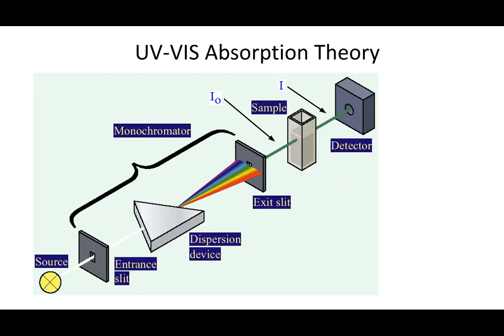The way UV-visible absorption spectroscopy works is you have a light source. The light goes through a slit just to make a beam, then through a dispersion device — usually a diffraction grating that acts like a prism — which splits the light up into a rainbow. A slit then allows only a certain wavelength of light to come through. This whole section is called the monochromator, meaning it selects a single wavelength, a single color of light.